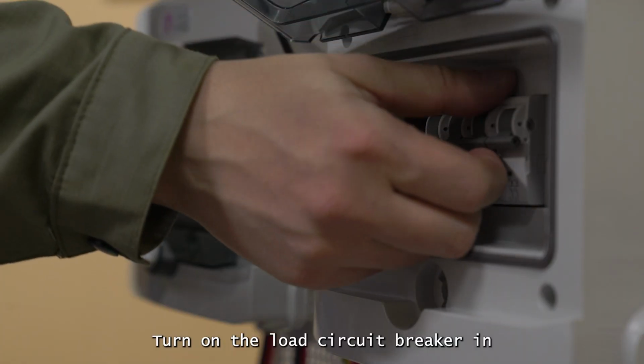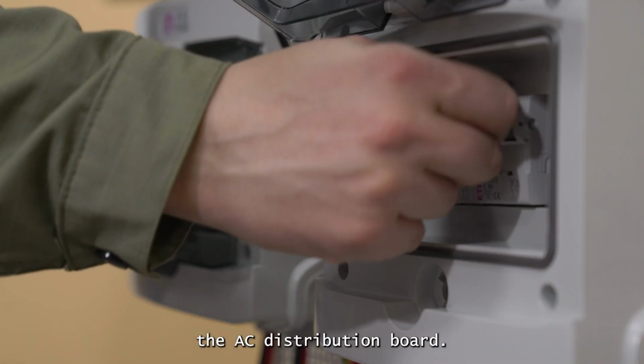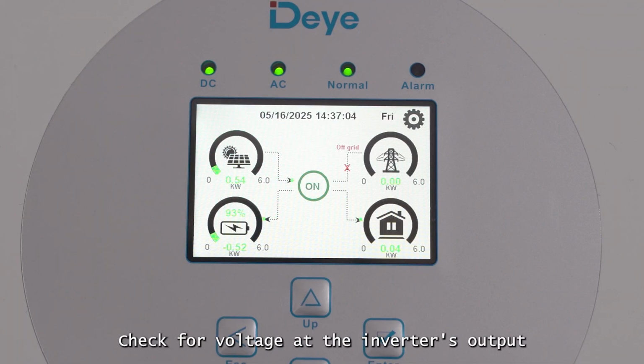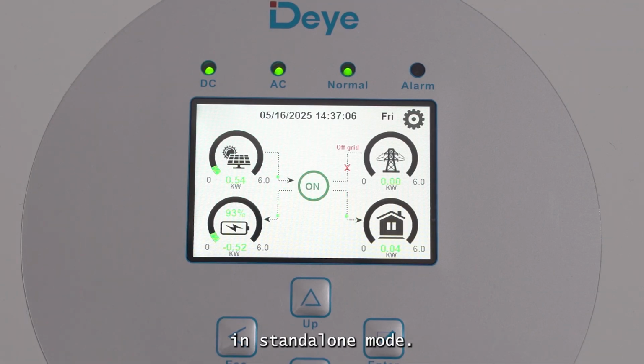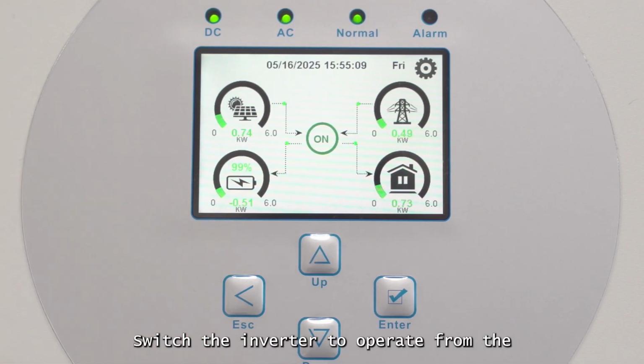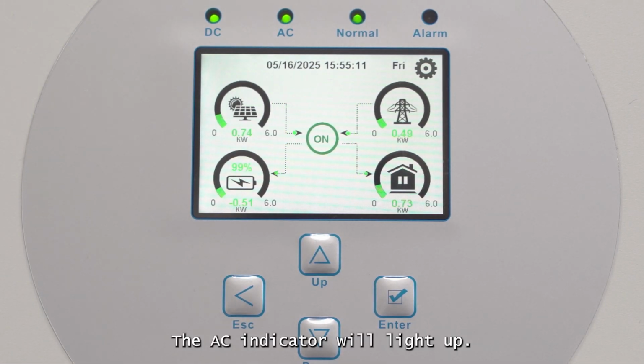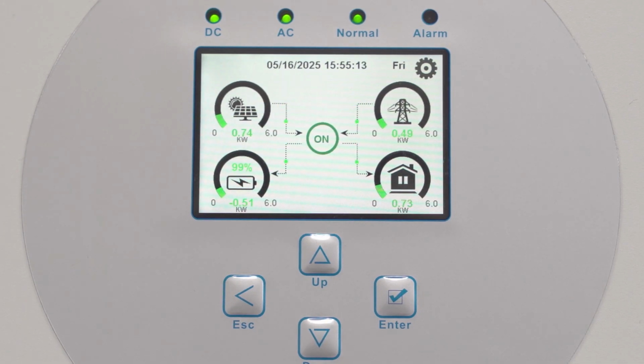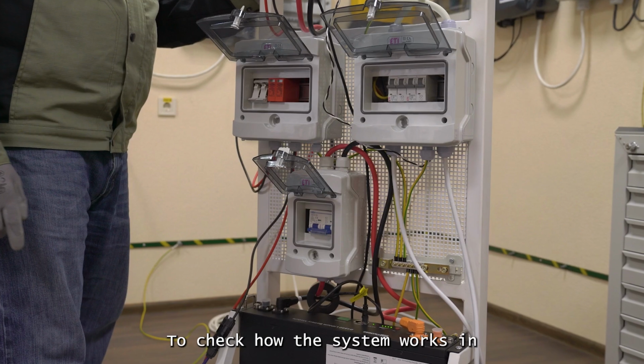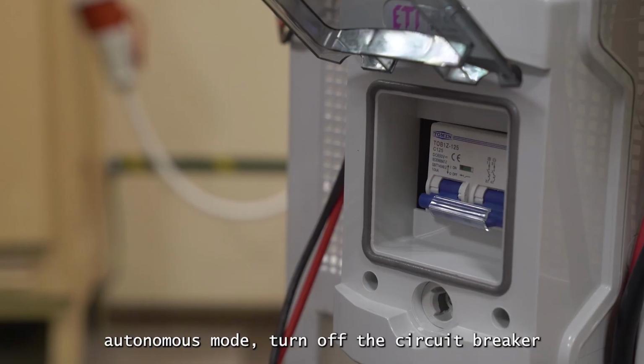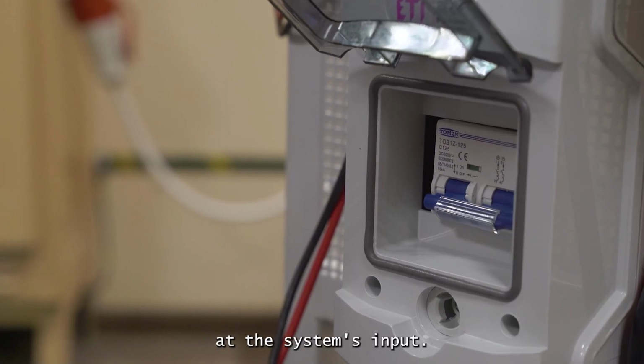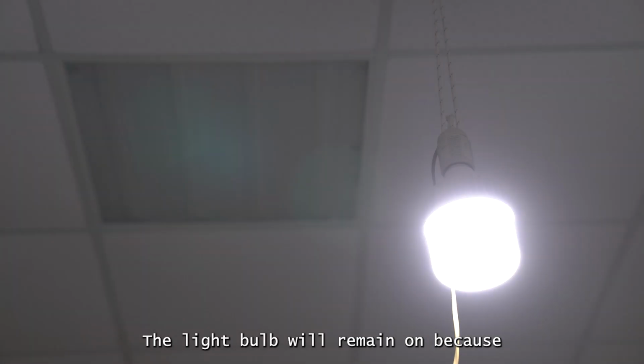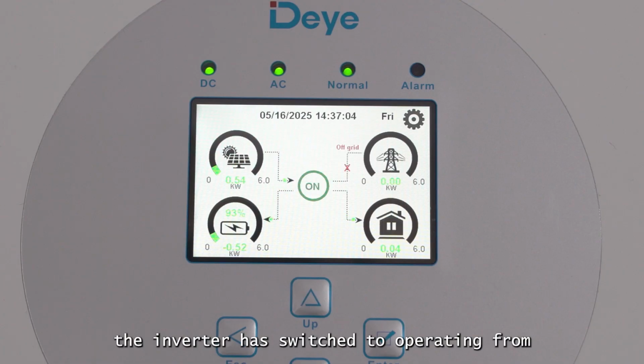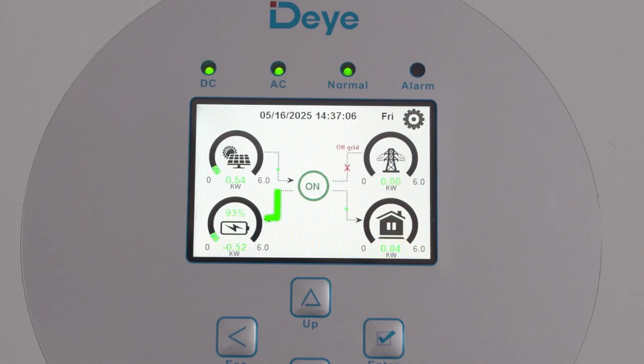Turn on the load circuit breaker in the AC distribution board. Check for voltage at the inverter's output in standalone mode. Connect a small load to the inverter, a light bulb. Switch the inverter to operate from the grid. The AC indicator will light up. To check how the system works in autonomous mode, turn off the circuit breaker at the system's input. The light bulb will remain on because the inverter has switched to operating from the battery.